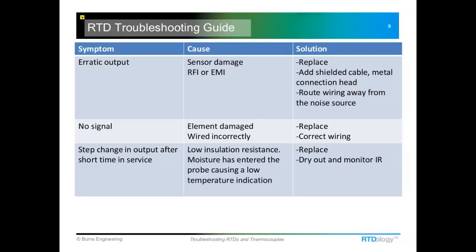How do you fix that? The probe can be dried out — take it out, put it in an oven. Vacuum ovens work a little faster; a couple hundred degrees Fahrenheit for maybe a day or two will dry it out. But you do have to ask how the moisture got in in the first place — maybe that epoxy seal has been compromised. It's a toss-up whether you try to dry the probe out and monitor the insulation resistance going forward, or just replace the probe.